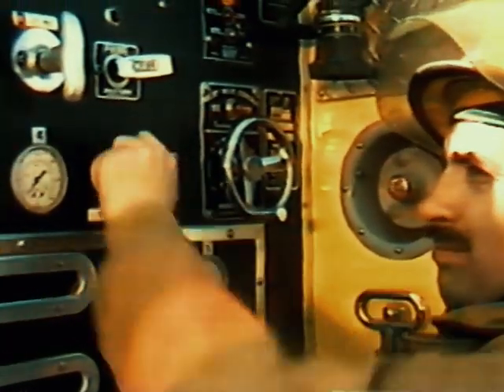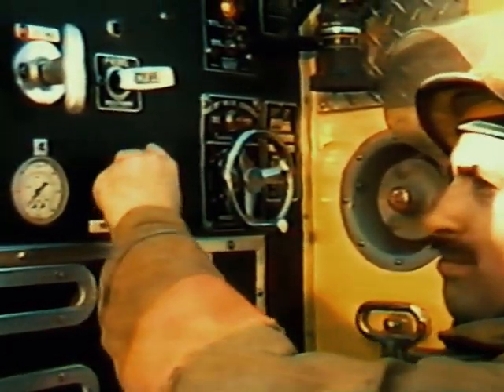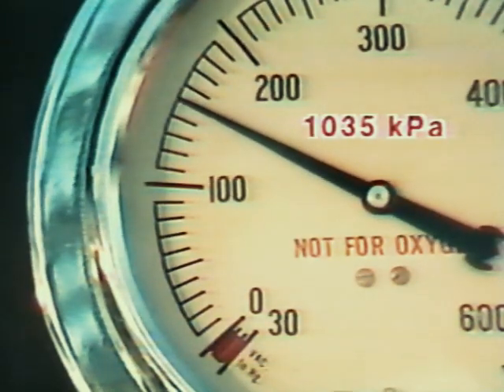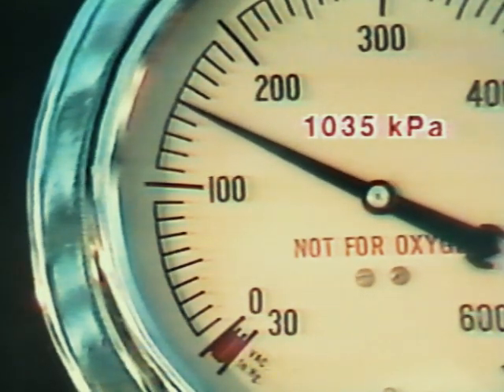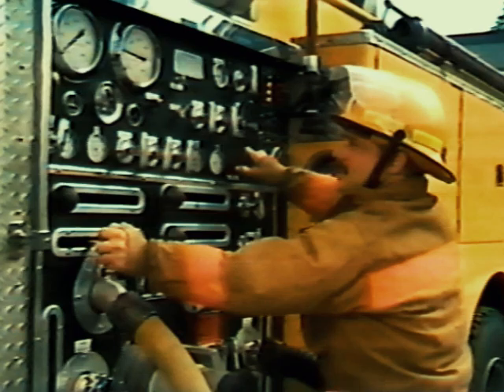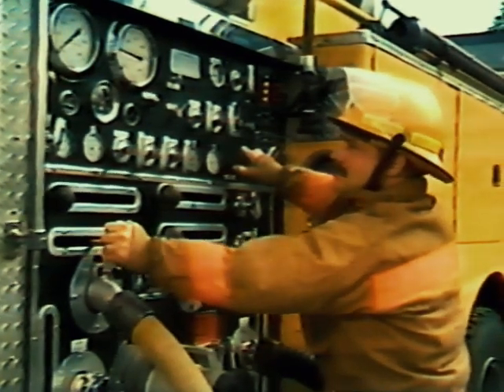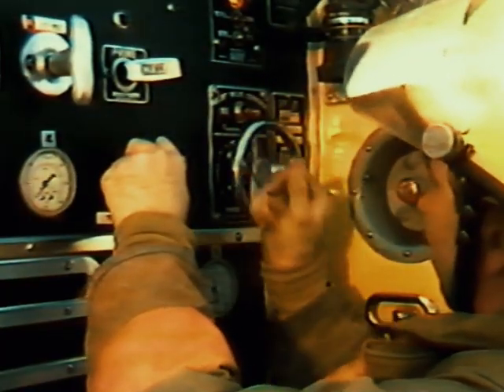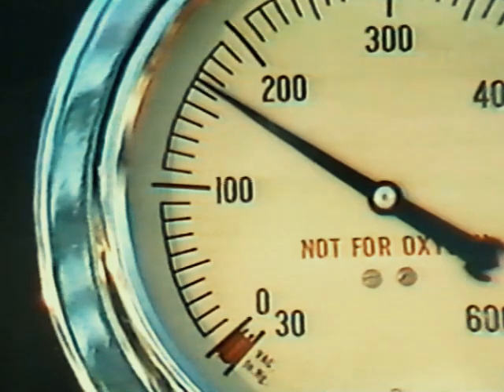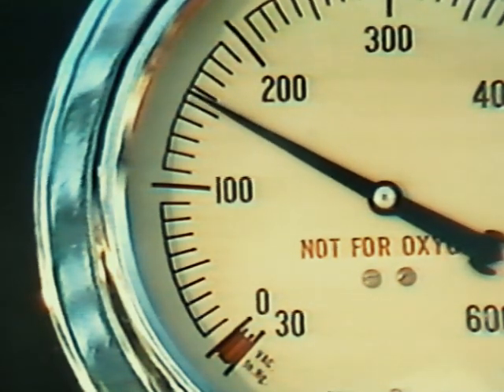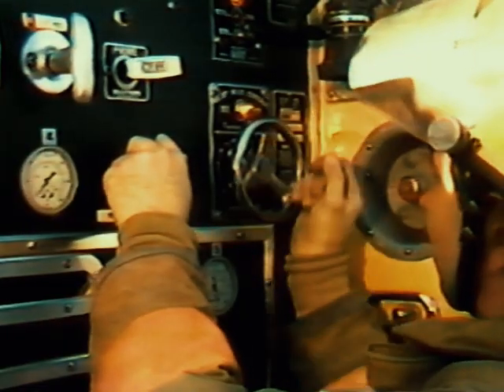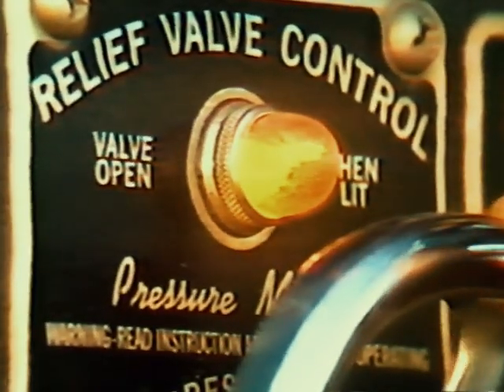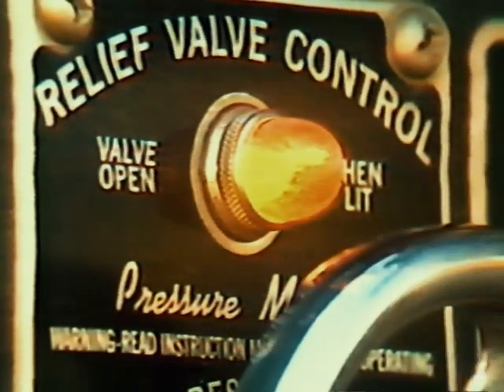To set a relief valve, bring the pump to a desired pressure, for example, 150 pounds per square inch. Make sure at least one discharge line is open, and turn the control handle counterclockwise until the pump pressure begins to drop and the pilot light comes on. The pressure drop and light indicates that the relief valve has opened and is bypassing water.